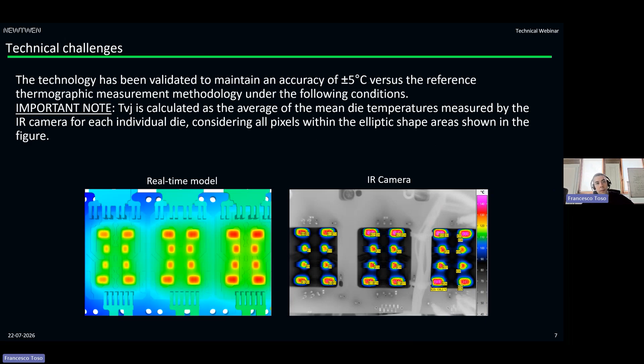For instance, it's important that during the commissioning test campaign, using the IR camera with a setup of this kind, we operate the inverter in different conditions, changing also the coolant flow, the boundary conditions such as coolant temperature, and also the power module itself, so that we collect test data, usually 4 or 5 full test bench campaigns.